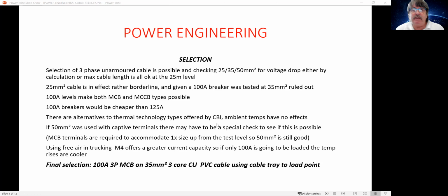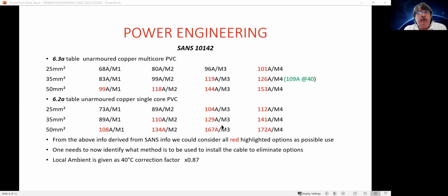So if we have a look at the tables in the SANS document, and you will get to that a little bit down here, let's have a look at those tables first. So if we have a look at 6.3a, unarmored copper multi-core PVC, typical 3-core type cable that we might be using. And we look at what we're given, M1, M2, M3, M4, the methods of supply, or where that cable could be laid or held or done. And we're not looking at any other techniques. We're looking at the basic technique here. We're not looking at things like multi-cables in ground, etc., which could have a knock-on effect here as well.